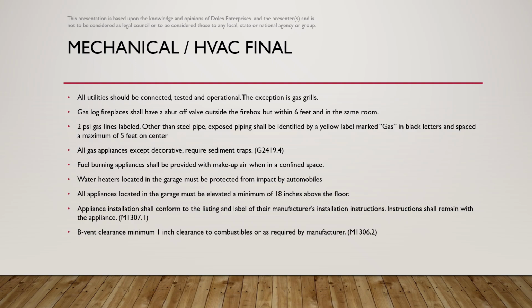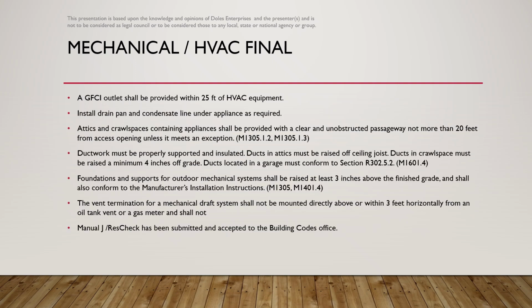Reference IRC Section M1306.2. Install drain pan and condensate line under appliances as required. Attics and crawl spaces containing appliances shall be provided with a clear and unobstructed passageway not more than 20 feet from access openings unless it meets the exceptions in the code. Ductwork must be properly supported and insulated. Ducts in attics must be raised off ceiling joists. Ducts in crawl spaces must be raised a minimum of 4 inches off grade. Ducts located in a garage must conform to section R302.5.2 and M1601.4.